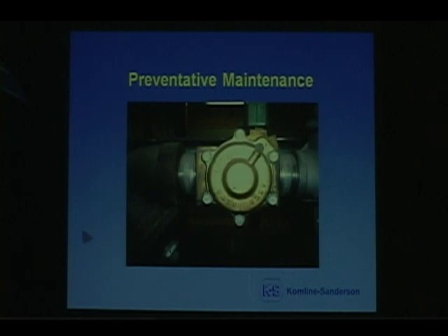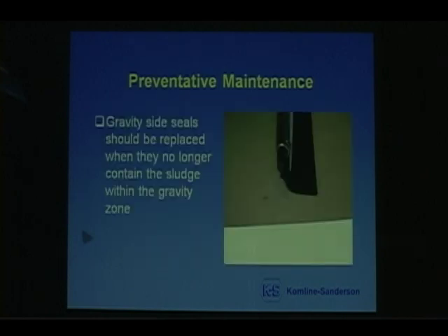Your wash water solenoid, ASCO recommends every 3 to 6 months you periodically take it apart, examine it, and clean it. Your gravity side seal is an extruded rubber seal. When it no longer contains the sludge within the gravity section, you need to replace it. One guy could pull it out, but you need 2 guys to replace it because the seal is embedded in a tube with a slot. If one guy tries to put it in, it gets hung up on the slot. So you need 1 guy to guide it, 1 guy to pull it.